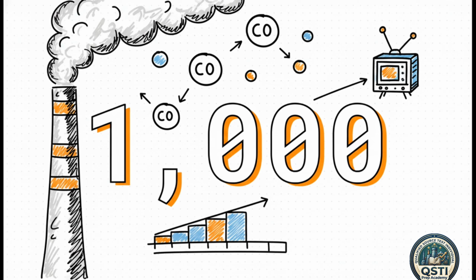Well, first, we've got to establish the baseline. The specification tells us that this particular test was developed primarily for systems with span values of 1,000 parts per million by volume of carbon monoxide. So that's the baseline scale we're working with when calibrating the system for these specific industrial facilities.